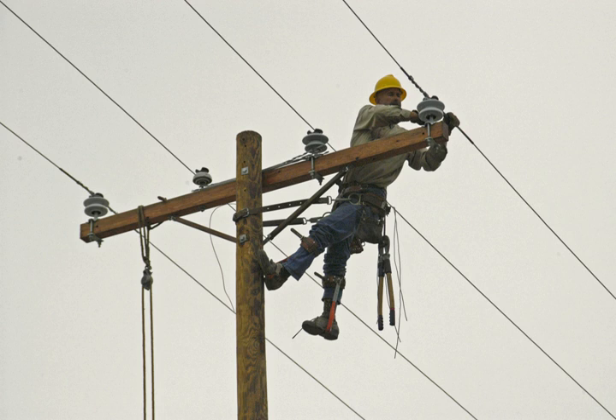All live line work PPE must be kept clean from contaminants and regularly tested for dielectric integrity. This is done by the use of high-voltage electrical testing equipment. Other general items of PPE such as helmets are usually replaced at regular intervals.